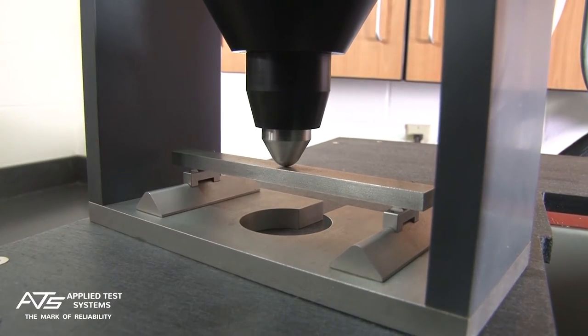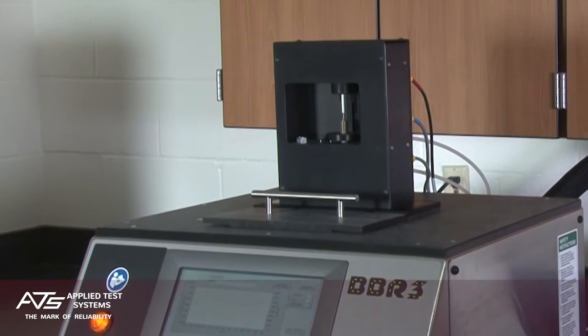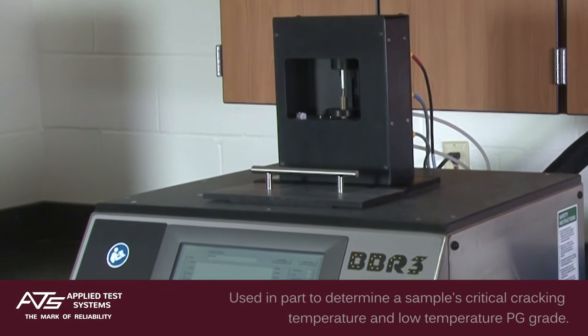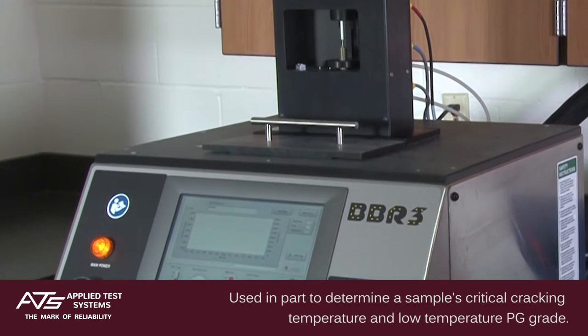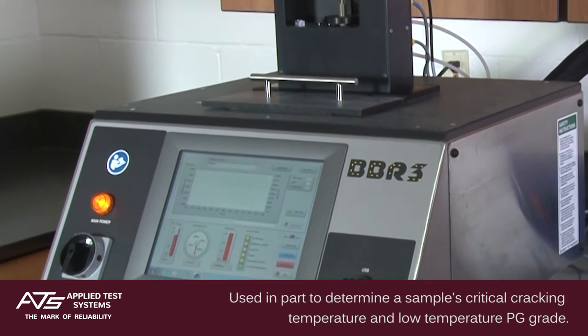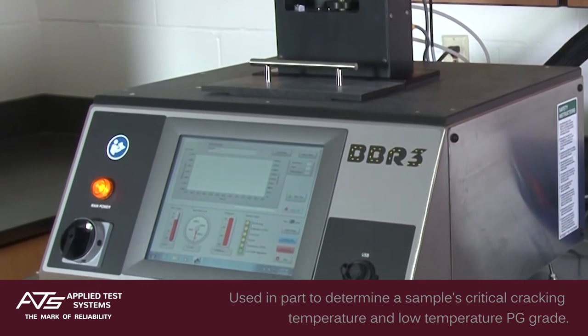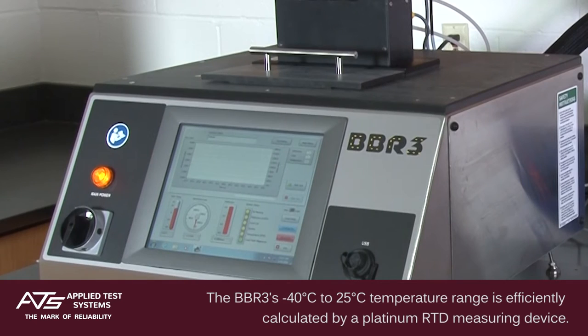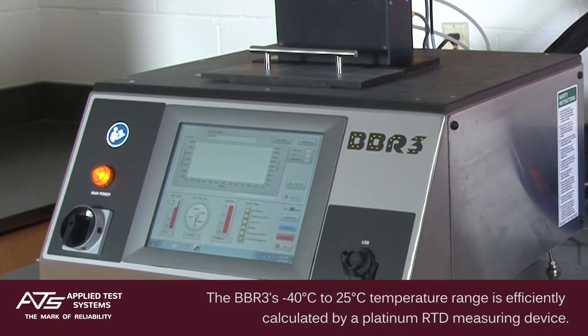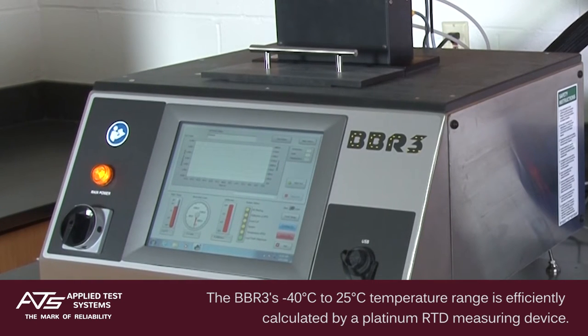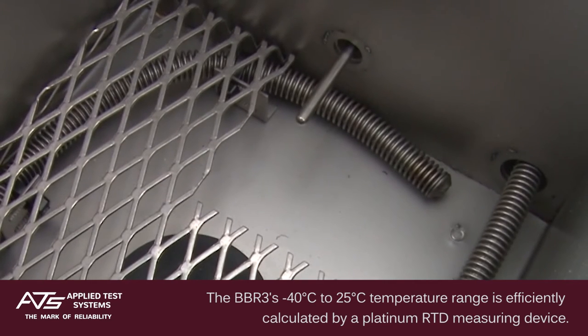Internal software calculates the flexural creep stiffness of the beam. Used in part to determine a sample's critical cracking temperature and low temperature PG grade, the BBR3's negative 40 degrees Celsius to 25 degrees Celsius range is efficiently calculated by a Platinum RTD measuring device.